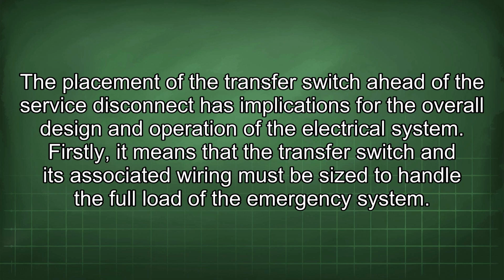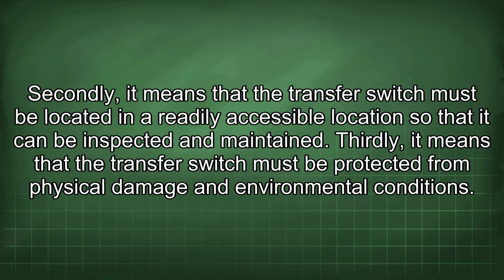Firstly, it means that the transfer switch and its associated wiring must be sized to handle the full load of the emergency system. Secondly, it means that the transfer switch must be located in a readily accessible location so that it can be inspected and maintained. Thirdly, it means that the transfer switch must be protected from physical damage and environmental conditions.